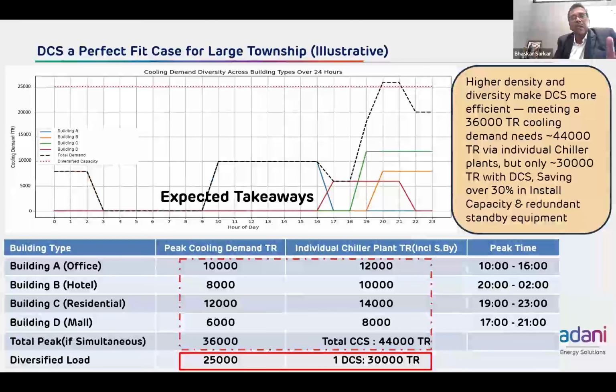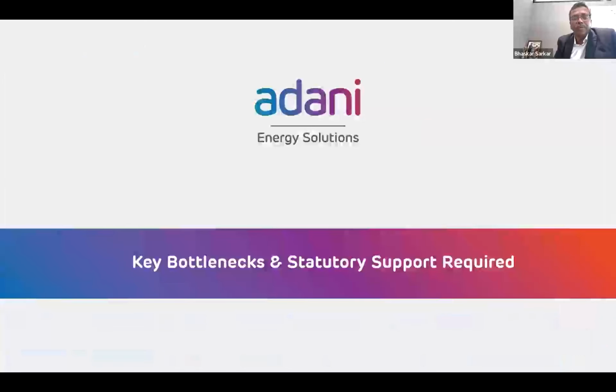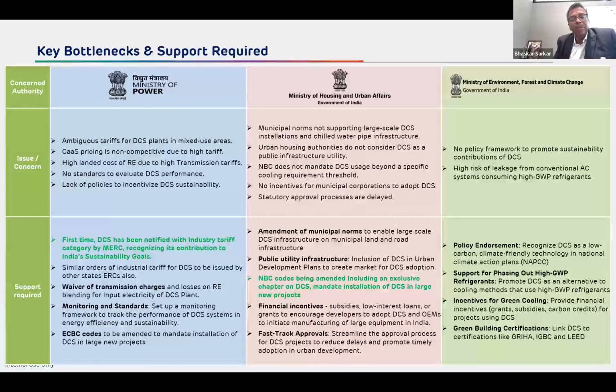stated. This is a large township illustration, whereby in a large township there are offices, hotels, residentials, malls, which would have needed 44,000 TR of capacity had they been conventional. But in a DCS system, we would have installed only 30,000 TR based on the peak demand and complementarity, and that would have saved a significant amount in all aspects. So this is one. And then next, I will just touch upon the various issues and concerns which we have been facing.